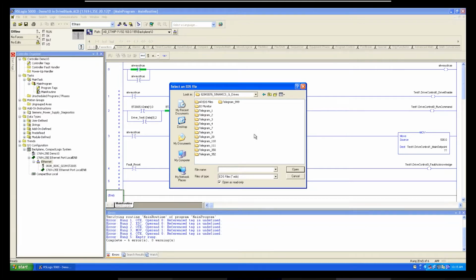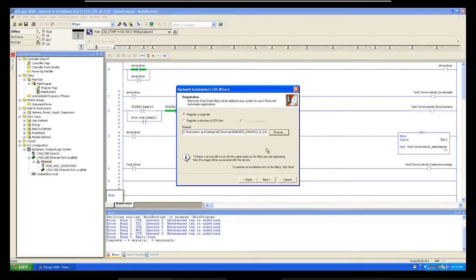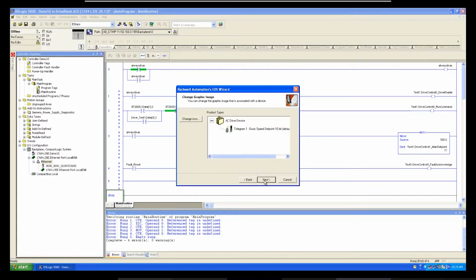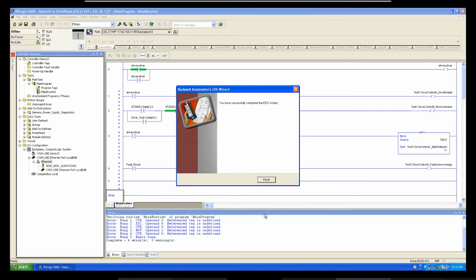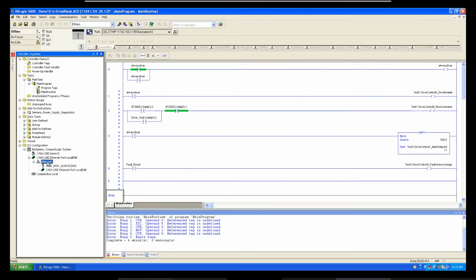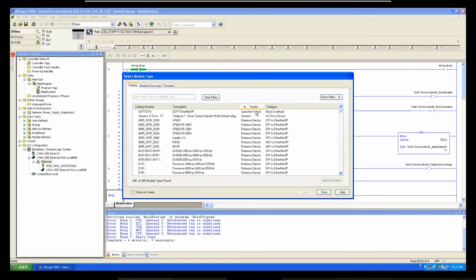So we're going to click in a little further. Because we set the drive up for Telegram 1, we're going to select Telegram 1, PLC EDS files, and select the Siemens G drive EDS. Open, next, next, and finish. Okay. And now we're going to add a new device. New module. Click Siemens Telegram 1 and create.